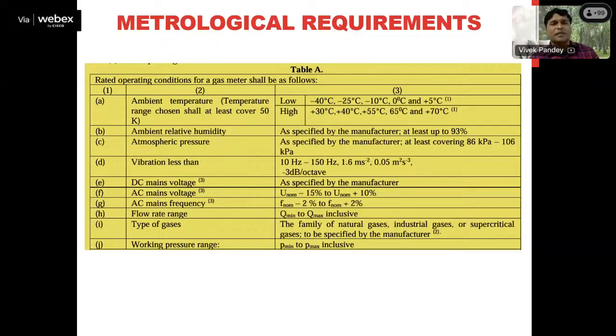Similarly, there are other parameters, like the voltage supply. For the AC voltage supply, the nominal supply is 240 volts; normally we get a single phase supply of nearby 240 volts. So a variation of plus minus 15 might be there for the lower voltage range, and the upper voltage level should be 240 volts plus 10. Okay, so it is nearby 264 volts, you can see. So this is one thing.